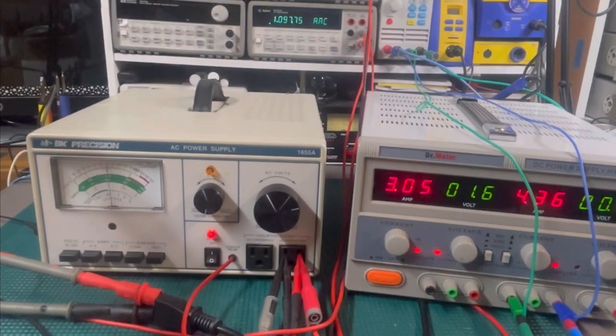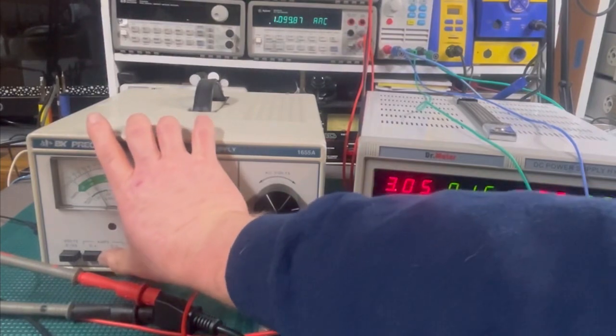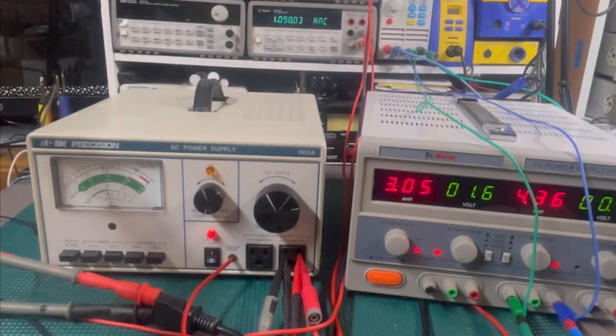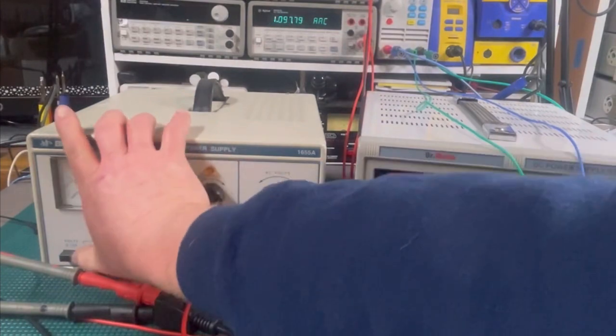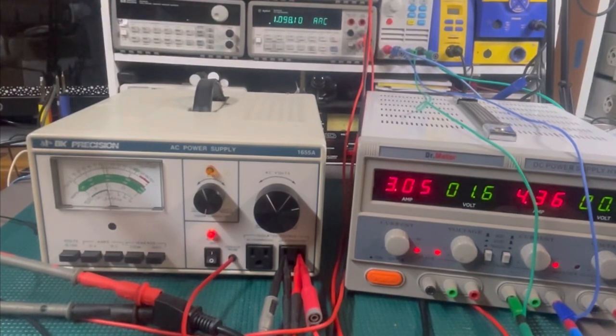Yeah, so there's something funky going on. Well, you know, especially AC amperage gauges, they're not highly accurate per se. But on the 1 through 4, it's accurate, but we try to get that higher resolution. Now we're down a little bit. So it's still acting funky. It works a hell of a lot better than the other one that has a broken gauge, but not much better, but at least I see the gauge move. That makes me feel better, I guess.